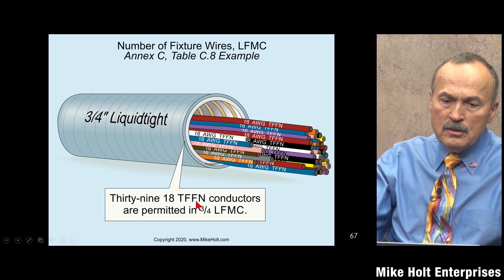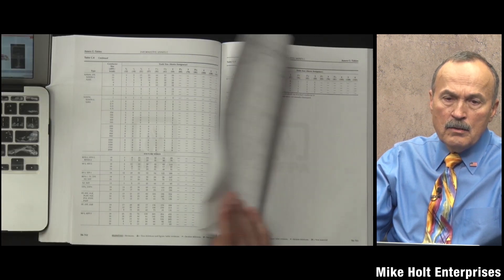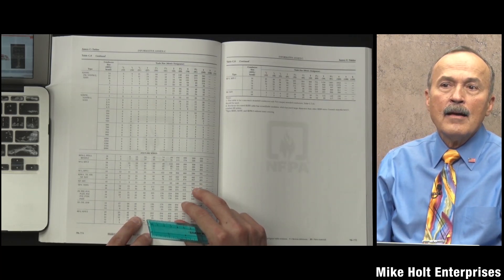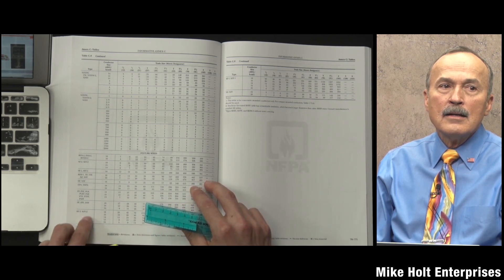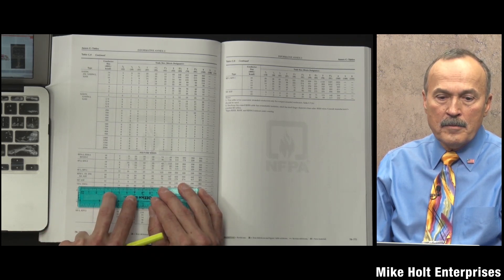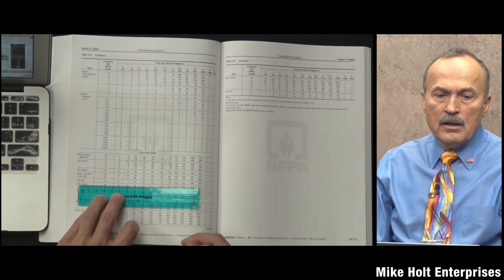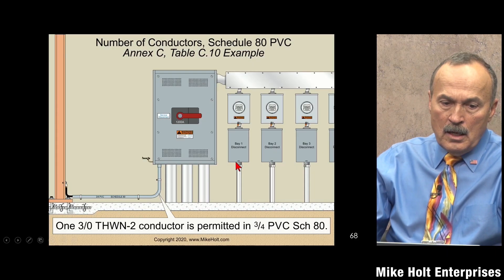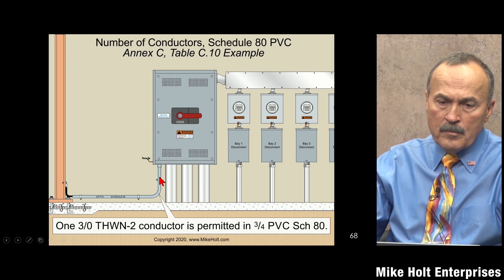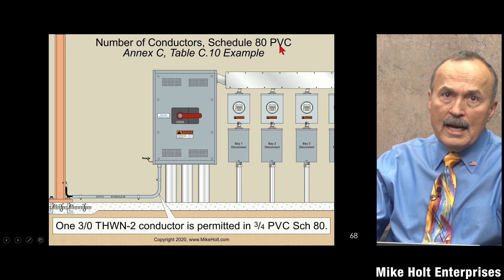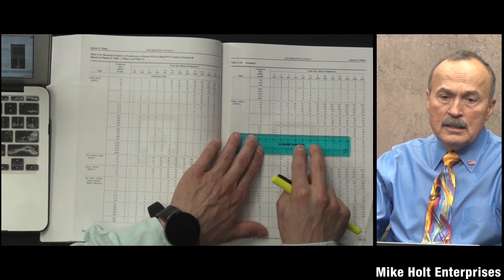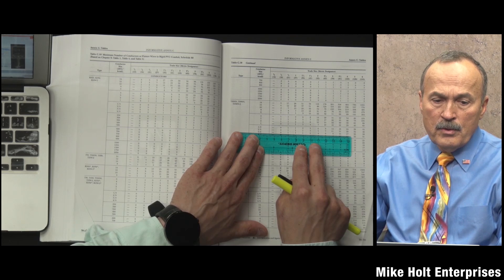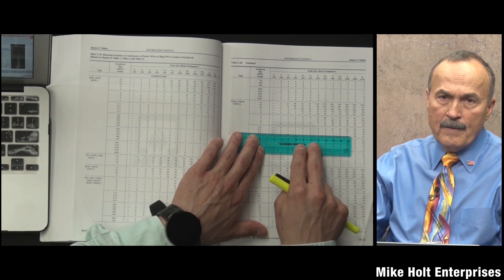Now fixture wires using Table C.8 for liquid tight: with 39 #18 TFFN conductors in 3/4-inch liquid tight, going to Table C.8 under TFFN 18 gauge - the answer is 39, so the graphic is correct. For a single conductor in a raceway, going to Annex C for PVC Schedule 80 - that's Table C.10 - a single 3/0 AWG THWN-2 conductor can fit in a 3/4-inch raceway.